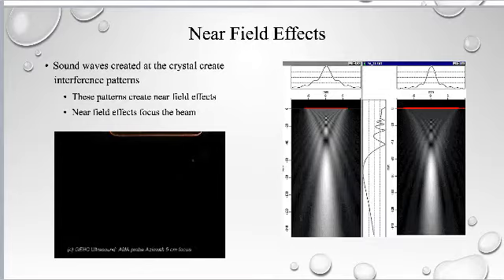When you say the near zone length, where is that again on the actual picture? Near zone length is from the crystal to the focus. Absolutely. From the crystal to the focus is the near zone length. Let's see if we got that picture somewhere here. There you go. We call it the focal length on this picture.